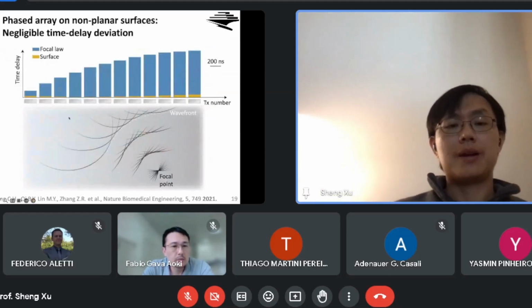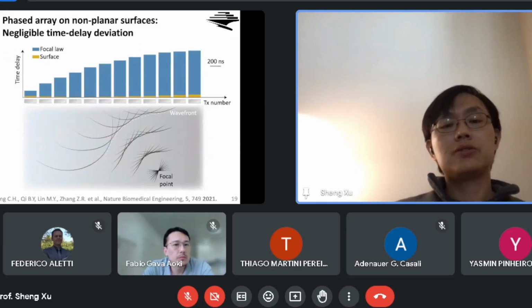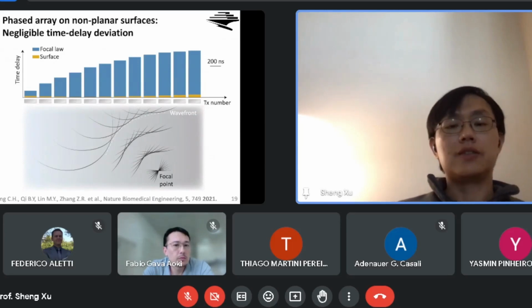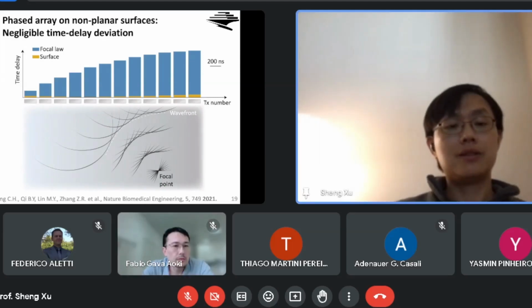So a good question you may ask is, well, the phased array requires activating the transducers with a certain delay profile. But what if you deform your phased array? Then you have to adjust your delay profile, right? If you do not know how your phased array is deformed, you cannot adjust the delay profile. So this is a good question. It's a grand challenge in the field. Lots of people in the world are working on this, and they have already published quite a few papers. I would say those solutions are great, but not perfect.